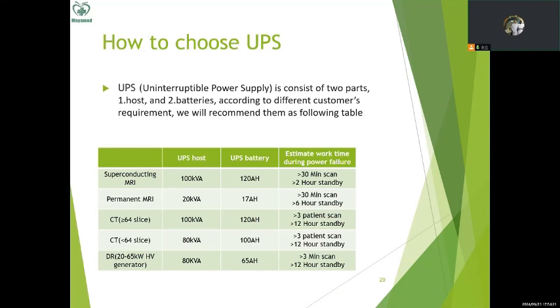So finally, for the DR system, 20 to 65 kilowatts high voltage generator, we can configure the UPS host according to the generator's power. For example, if we configure a 50 or 65 kilowatt high voltage generator, we recommend to use an 80 kVA host of the UPS, and we configure a 65 Ah battery, which can support 3 minutes scan or 12 hours standby.